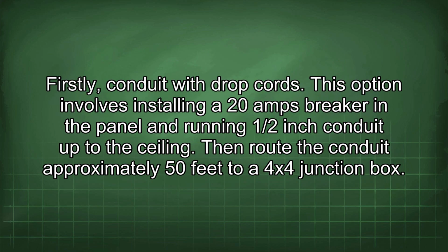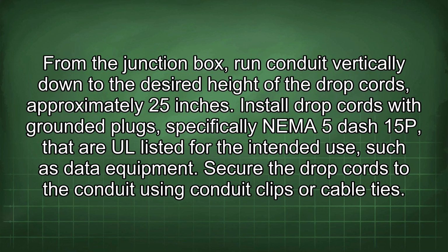Firstly, conduit with drop cords. This option involves installing a 20 amps breaker in the panel and running 1/2-inch conduit up to the ceiling. Then route the conduit approximately 50 feet to a four-square junction box. From the junction box, run conduit vertically down to the desired height of the drop cords, approximately 25 inches. Install drop cords with grounded plugs, specifically a 5-15P, that are UL listed for the intended use, such as data equipment. Secure the drop cords to the conduit using conduit clips or cable ties.